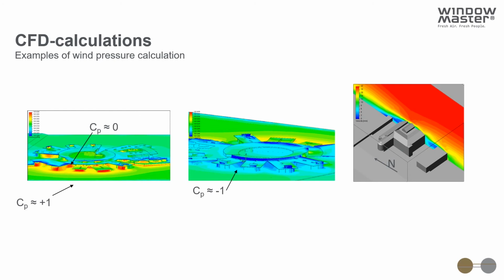At the point we're appointed onto the contract, we get a full set of drawings of the site and building, and build up a 3-dimensional model to which we apply a CFD analysis of the wind pressure. The data from this file is then built into the head end and allows us to make decisions when there is a demand for ventilation of space.